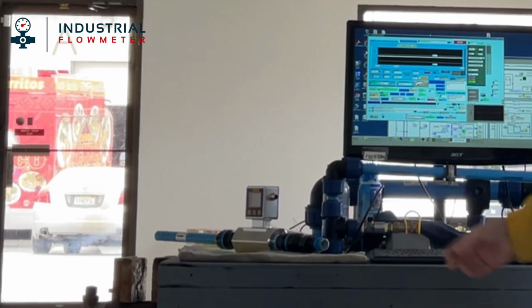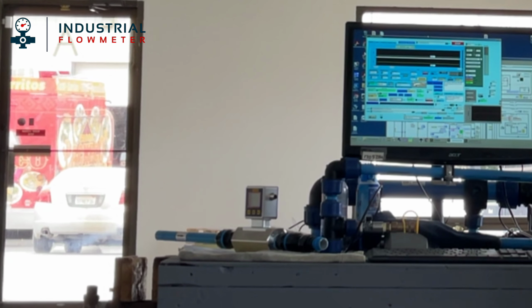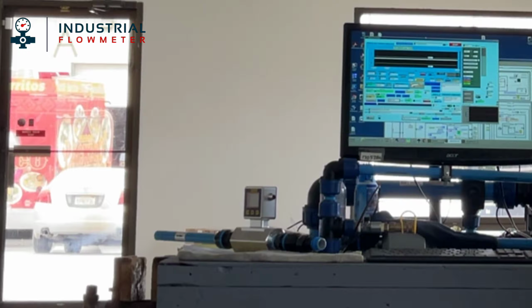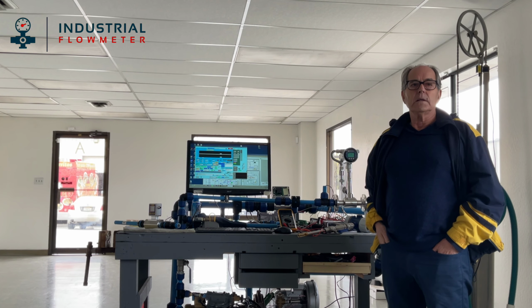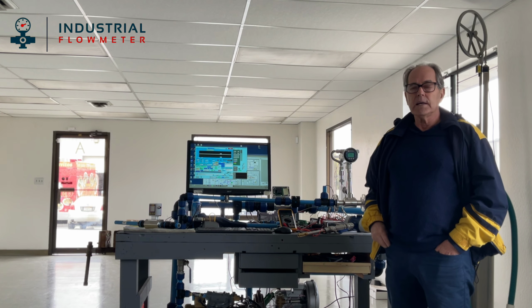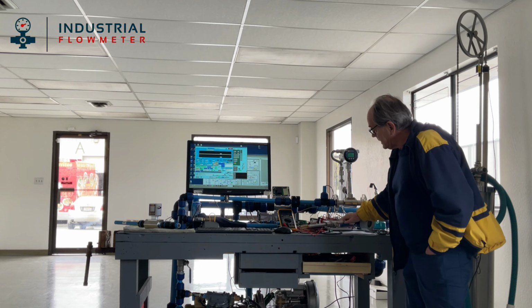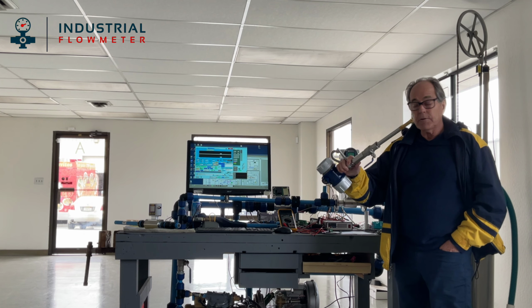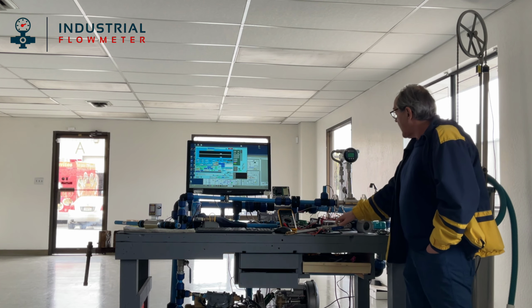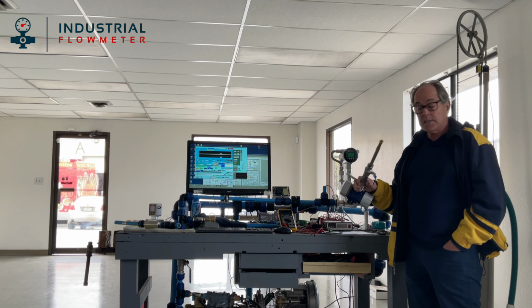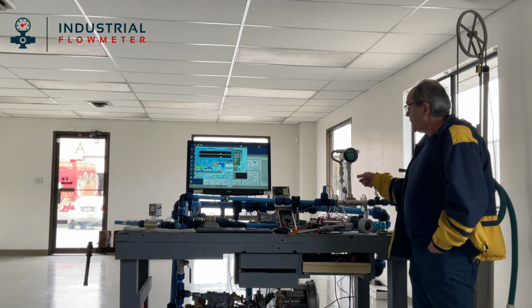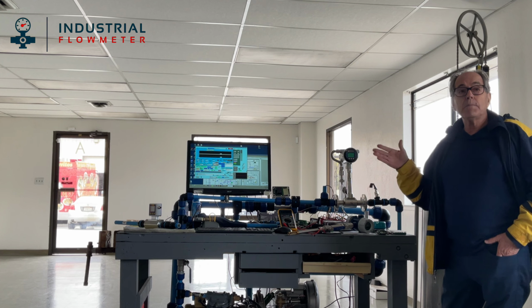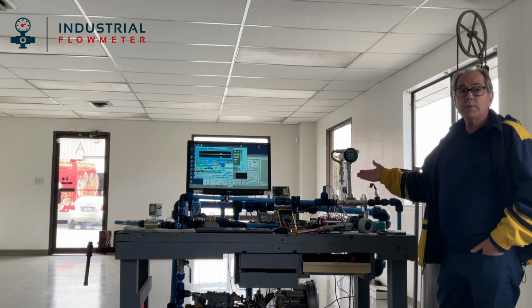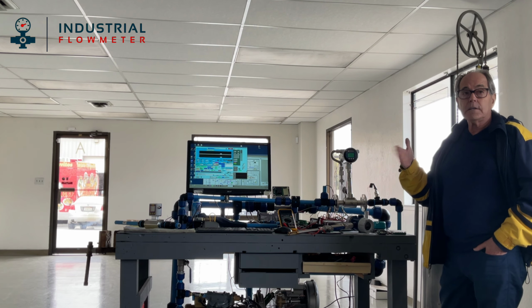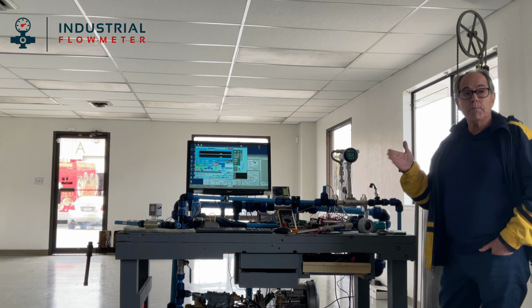And by characterization, we mean essentially mapping an output of the sensor to a flow rate. Yeah. So we're characterizing it by saying 0.3 volts equals 3,000 gallons per minute, and 0.1 volt equals this many gallons per minute. And that would be something for here, but this guy speaks volts, let's say. This guy speaks frequency, because it's fundamentally a time domain machine. And it's not a pretty square wave.